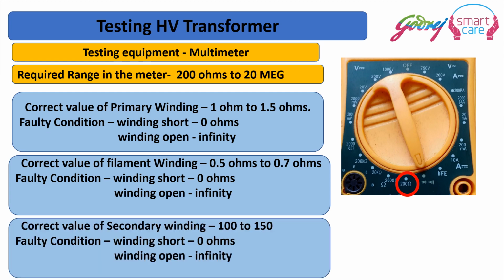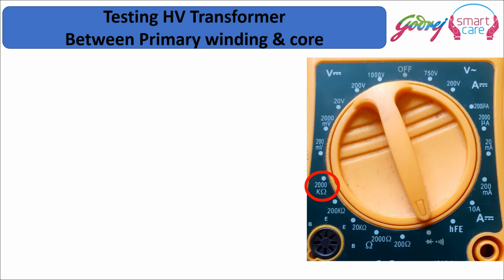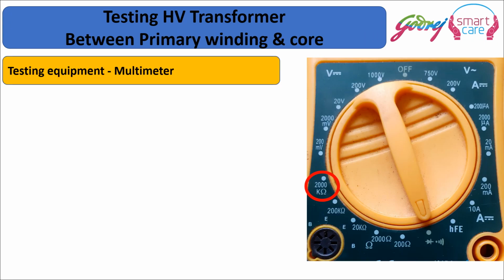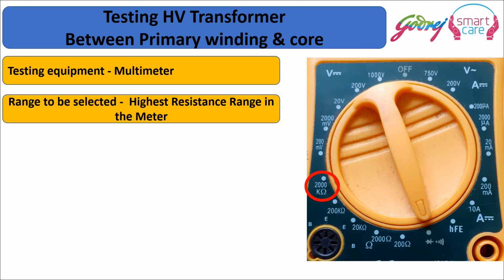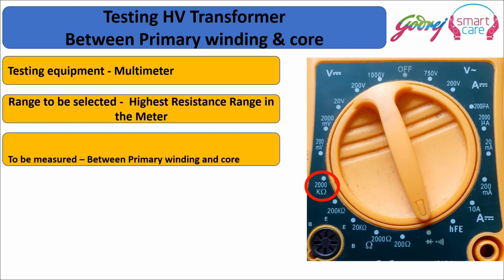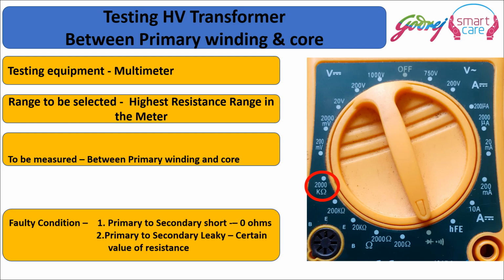Coming to the secondary winding, step-up winding. Step-up winding resistance should be 100 to 150 ohms. In the faulty condition again, the winding short will show 0 ohms and winding open will show infinity. Between primary and the core, select the highest resistance range in the meter and measure between primary winding and the core. The primary winding to secondary, if it is short, it will show 0 ohms. Primary to secondary leaky will show a certain value of resistance. Because primary and the secondary winding should not be short, neither should it be leaky.